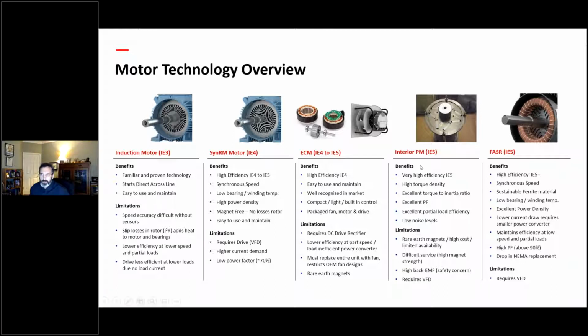And someone asked me one time, well, why doesn't everybody use ferrite magnets? Well, because rare earth magnets, like if you look at this interior PM motor, how many magnets do I got? 1, 2, 3, 4, 5, 6. You got 8 magnets in that motor. How many do I got in here? Probably 32 or so. They're less powerful. So you need a lot more magnets in the motor. So they're typically only practical in the lower horsepower range, or if you want to get a very small power dense motor like this EC motor over here, because you don't have to use much magnets at all.